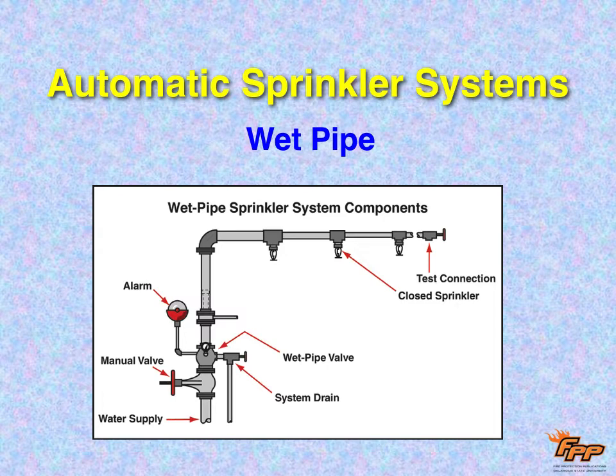Well, how does it turn on? Each sprinkler head has a glass bulb with a little chemical inside it, or it has a fusible link. The fusible links have solder that melts at certain temperatures. So the bulb or the fusible link ruptures at a certain temperature. When it breaks, a little cap that's being held in place by it falls off. Now the water will come out of the hole in the sprinkler head. It hits the deflector, which is the part that shoots the water out into an umbrella circle around the sprinkler head, and it'll come out at the rate that it's set to come out. That's a wet pipe system and how it works.